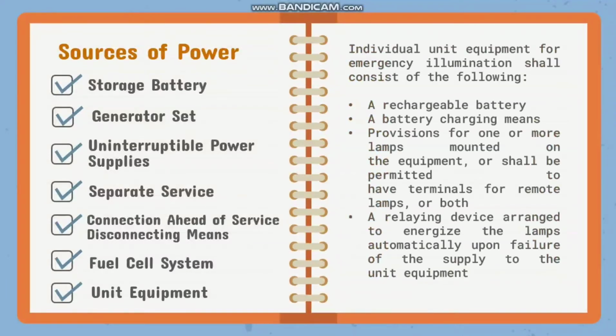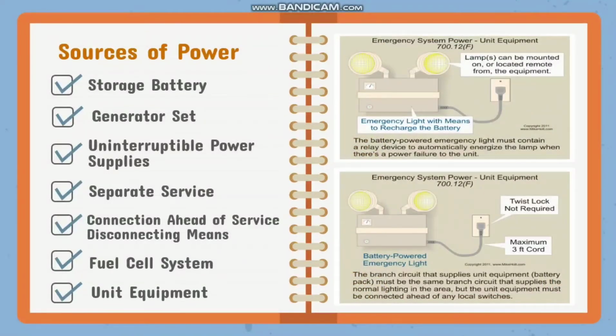Individual unit equipment for emergency illumination shall consist of the following: a rechargeable battery, a battery charging means, provision for one or more lamps mounted on the equipment or shall be permitted to have terminals for remote lamps or both, a relaying device arranged to energize the lamps automatically upon failure of the supply to the unit equipment. So lamps can be mounted on or located remote from the equipment. An emergency light with means of recharge to recharge the battery.